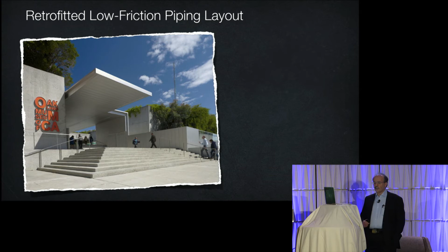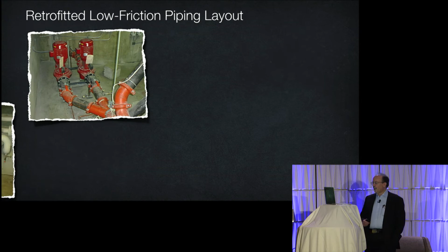At California's Oakland Museum, our colleague Peter Rumsey retrofitted an efficient piping layout into the condenser water pumping loop, cutting the pumping energy by three-quarters with a two-or-three-month payback, and eliminating 15 pumps that will never again waste energy and maintenance costs.